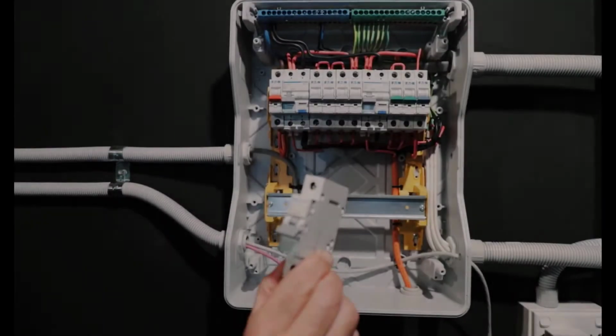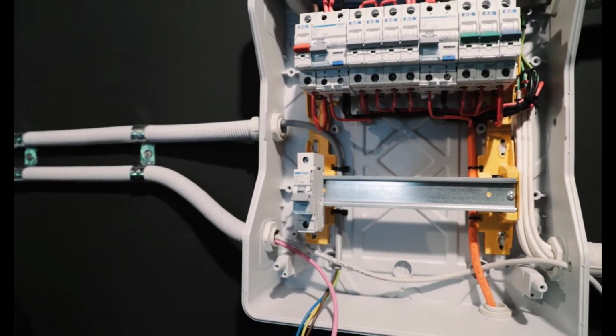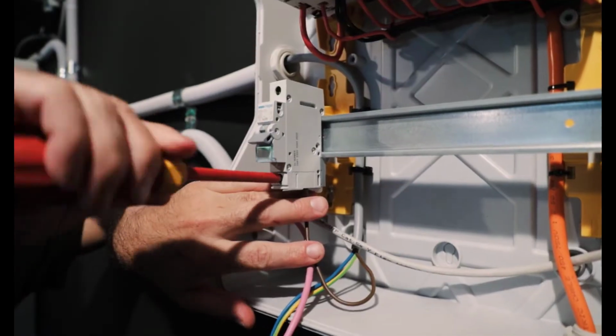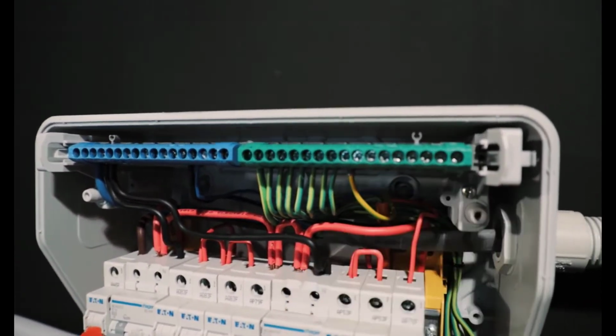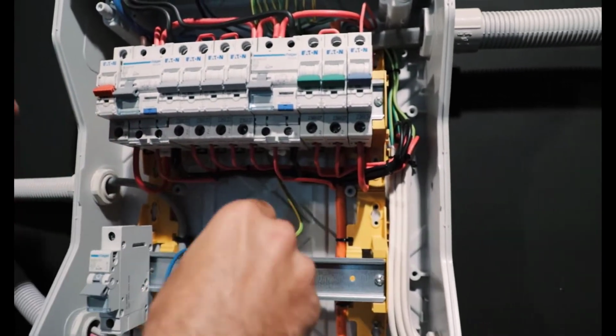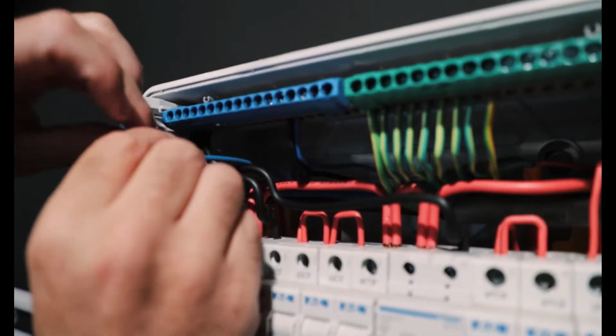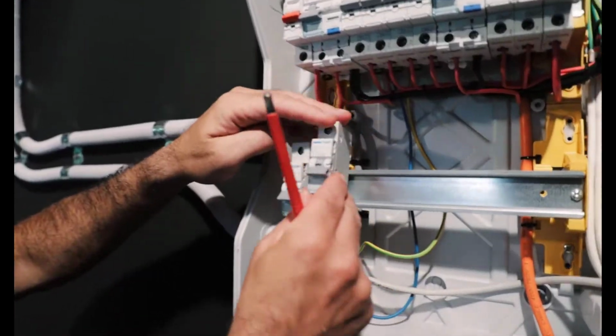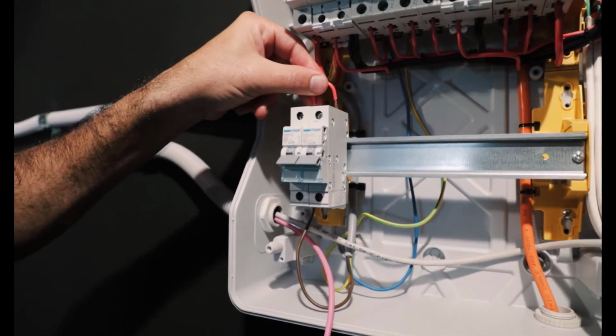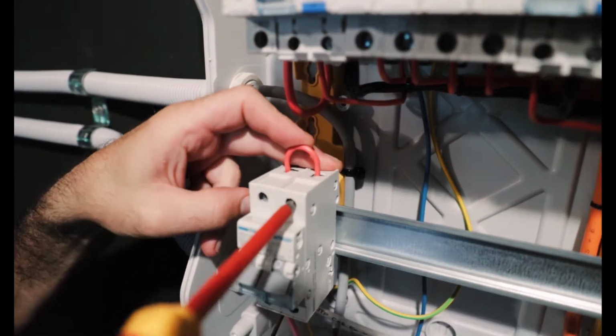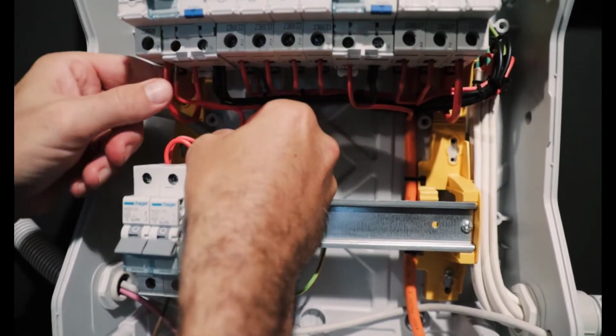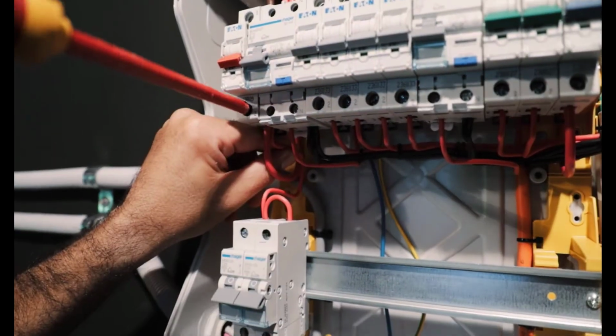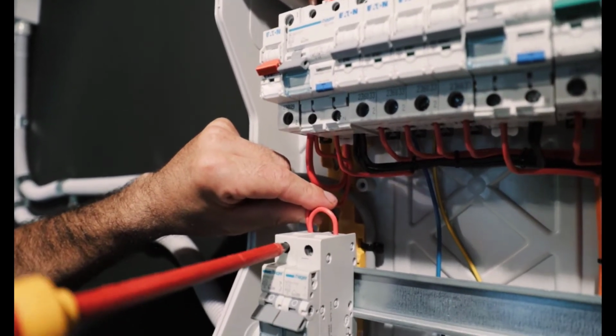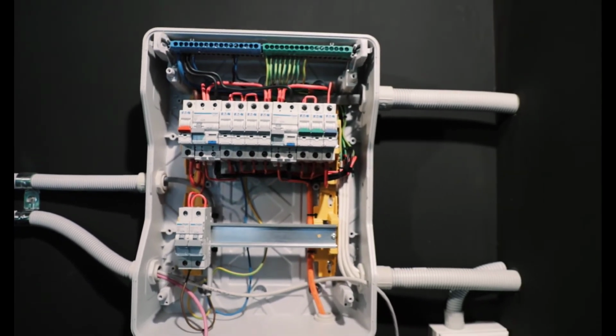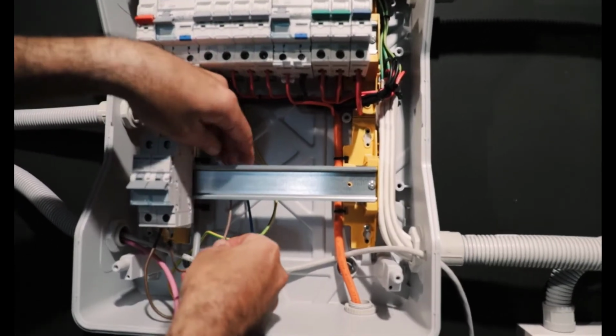So this is the first, probably the simplest of the AC connections for the hybrid 9.53. Okay, so AC is in. We've just wired the MCB there for the power going to the meter itself, and just tapping that end to the bottom of the main incoming supply from the grid. So as you can see, the switchboard here has been pre-wired. AC comes in, main isolator, then off to all the load circuits, and the PV is part of the load circuitry. So the PV could even be on a subboard.